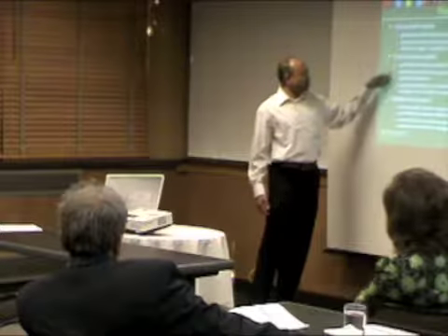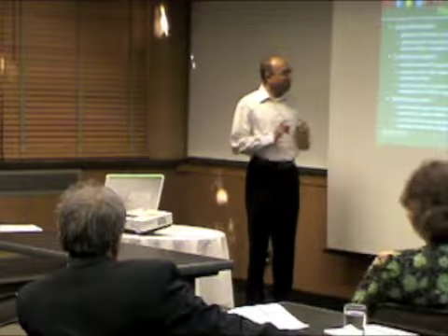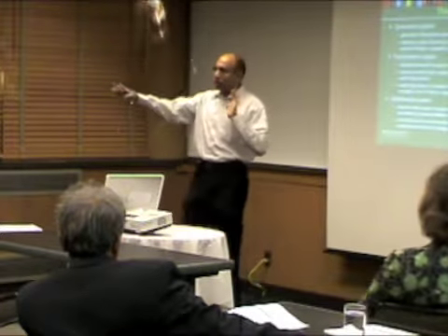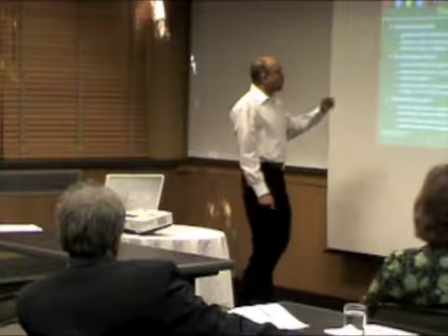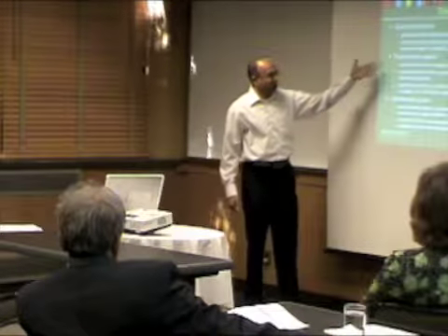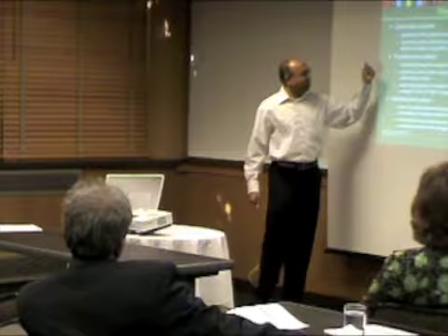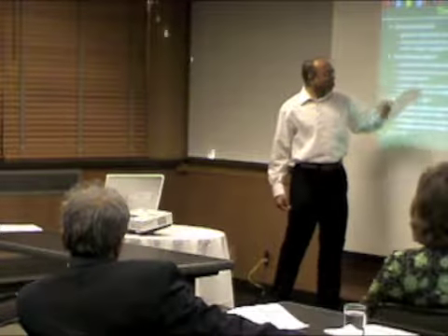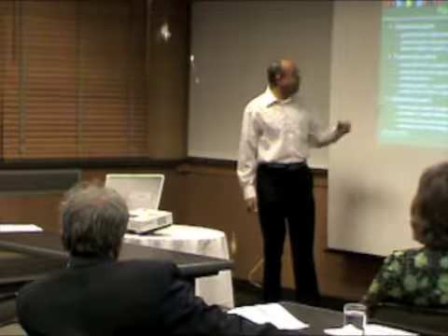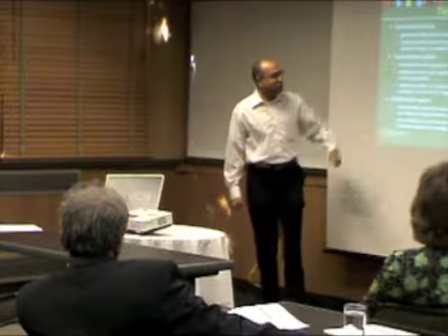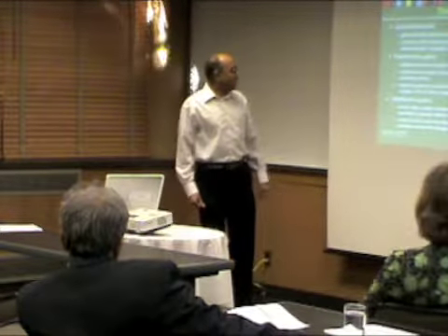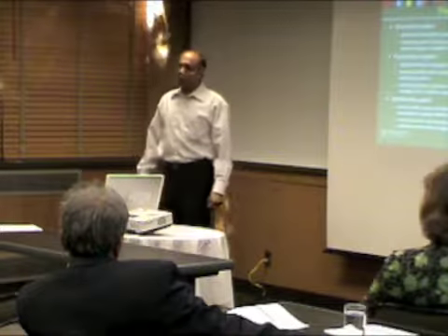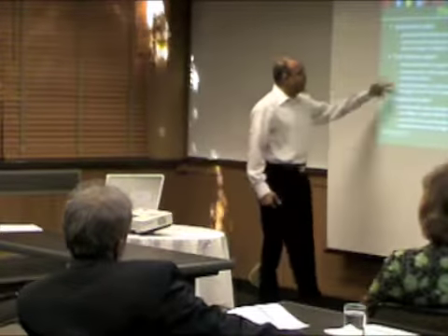The transmission system is a meshed network. It has some loops. Okay, it's not radial in that power does not necessarily flow in a single direction all the time. That's why, because it's meshed, it's also called the grid. And I'll come to that on the next slide. It transports three-phase power at 115 to 765 kV, and interfaces with other transmission lines and sub-transmission lines at switching stations. And switching stations connecting to sub-transmission lines step down the voltage to the 20 to 69 kV range.